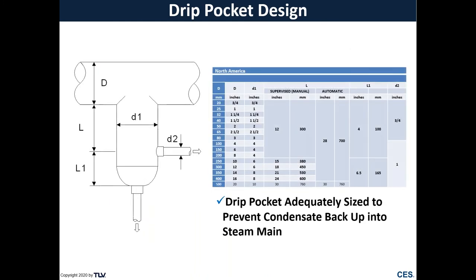So here's an example of condensate drip pocket sizing. We want to make sure that we have the appropriate diameter as well as depth of that pocket to allow that condensate and dirt to fall out of our system. Because if we make that pocket too small, that condensate can basically pass right over it and we can carry that condensate down our system, which can lead to erosion and potentially even water hammer.